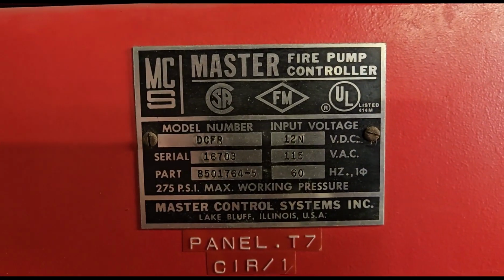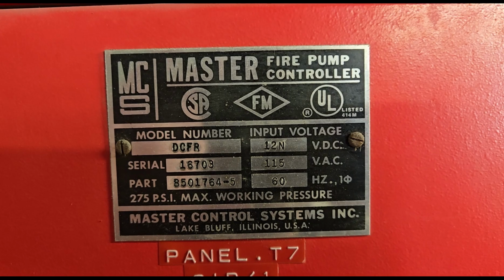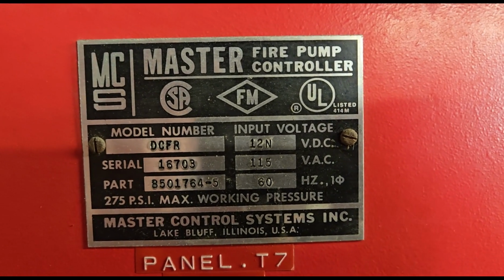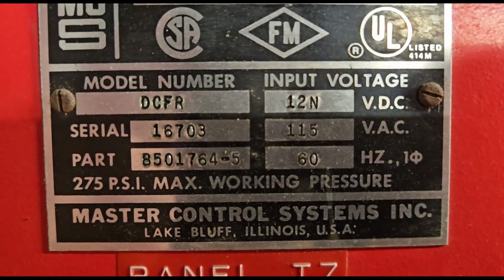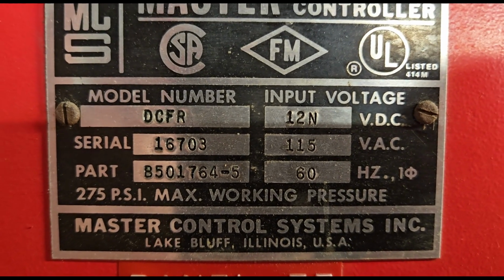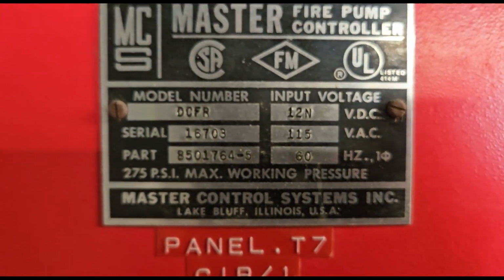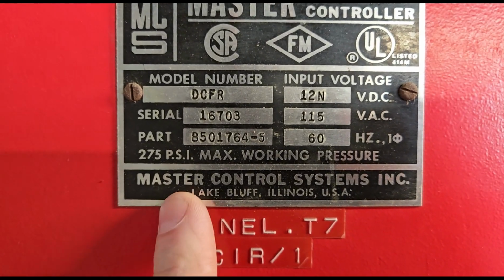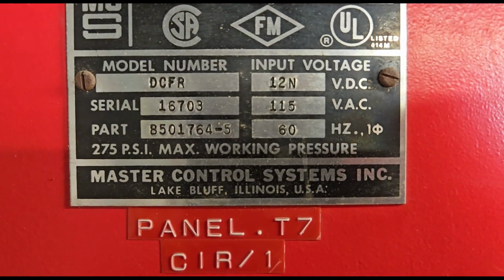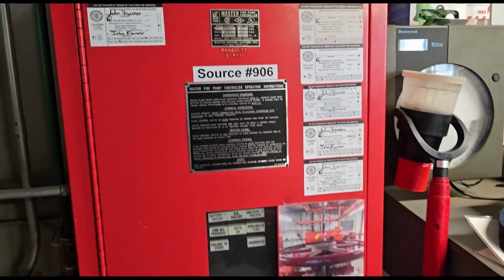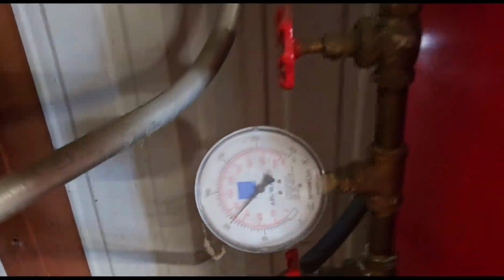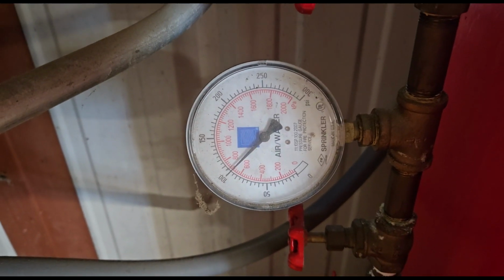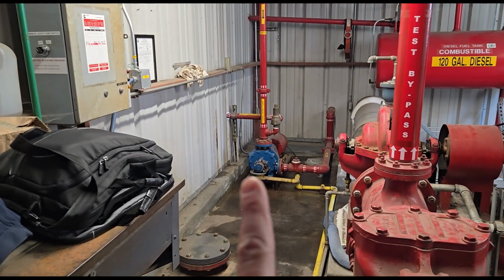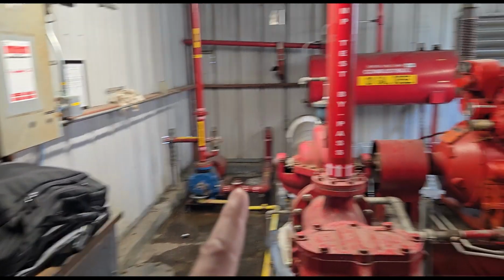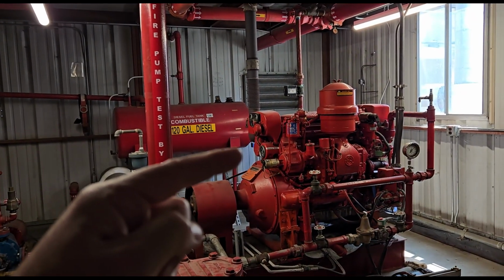So again, just for context, here we have the master fire pump controller. There's the model number, DCFR, by Master Control Systems Inc. And again, always check your PSI, make sure you're back up to where you started, otherwise the pump will kick on. So again, the jockey pump did all the work today. This little guy in the corner, you heard it running earlier, and we left this one off because we don't want to run it while we're here.